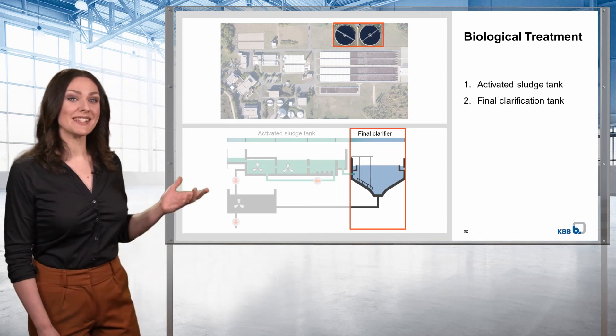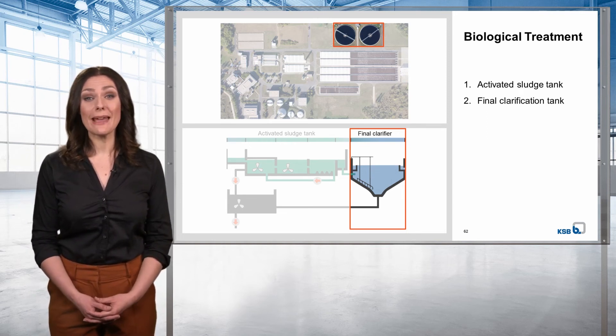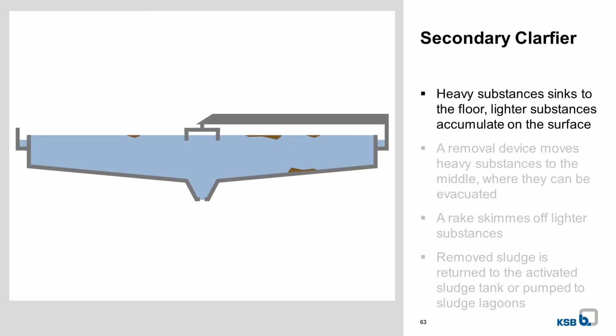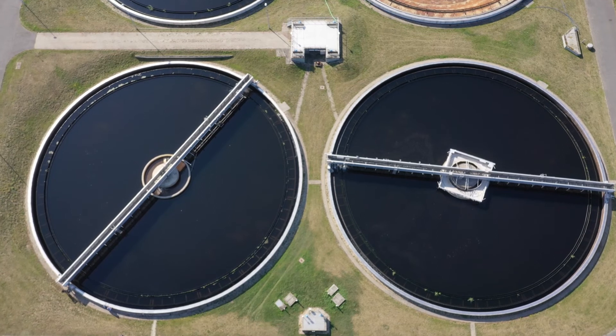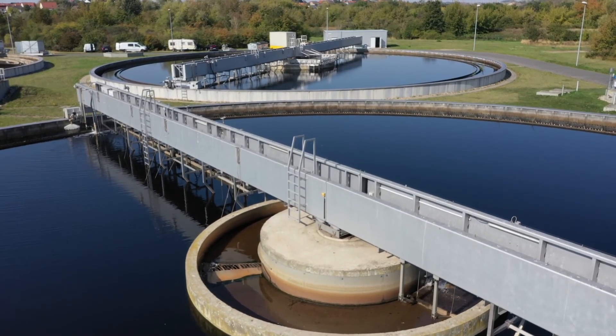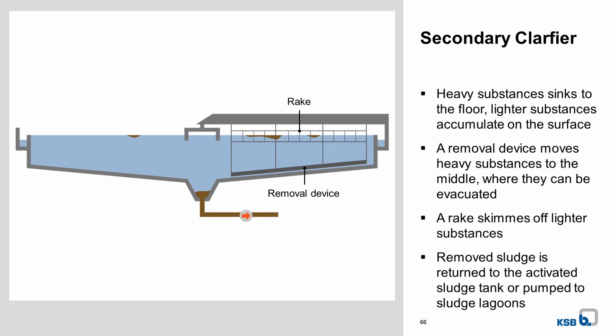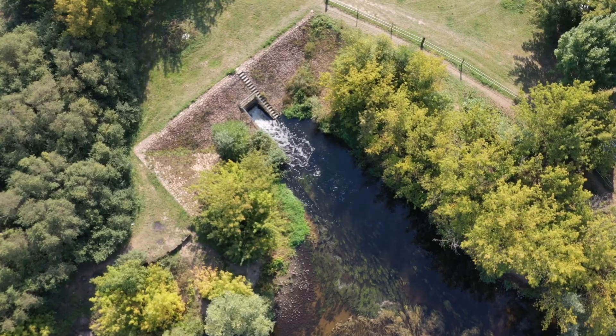Let's move on to the final or secondary clarifier, the last stage of biological treatment. The aim of this stage is to remove the microorganisms remaining in the water. Treated water flows continuously from the activated sludge tank into the final clarifier. Heavy sludge containing microorganisms sinks to the floor and lighter substances accumulate on the surface. A removal device moves the heavy substances to the middle so they can be evacuated, and the lighter substances are skimmed off by a rake. The removed sludge is either returned to the activated sludge tank or pumped to sludge lagoons, and the clarified water flows out via a drain channel. Everything taking place in biological treatment generally also occurs in nature — the only difference is that in wastewater treatment plants, the processes are carried out on an industrial basis.